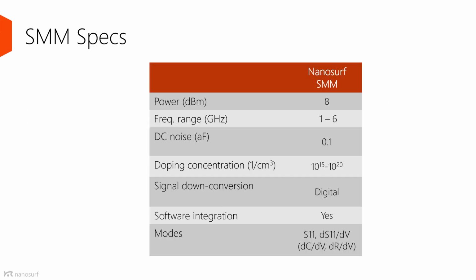Here are all the important parameters of the SMM electronics in one table. We have the power of 8 dBm, the frequency range of 1 to 6 GHz, the noise of DC capacitance is 0.1 attofarad, the control of the electronics is integrated in our software, and the measurement modes are S11 and the dS11/dV mode, from which you essentially get the dC/dV and the dR/dV mode.